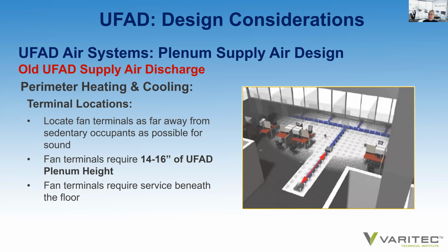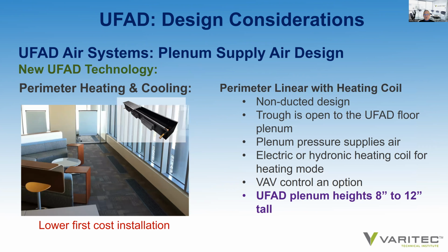Now, there could be an application in an office building or in a building with conference rooms that might suffer large load swings, going from 0 occupancy to 20 occupants very quickly for a meeting, where a fan-powered strategy could be considered, but we would certainly want to work with the design team in doing that. But anyway, this is very much an older strategy today compared to the newer technology that I'm about to demonstrate.